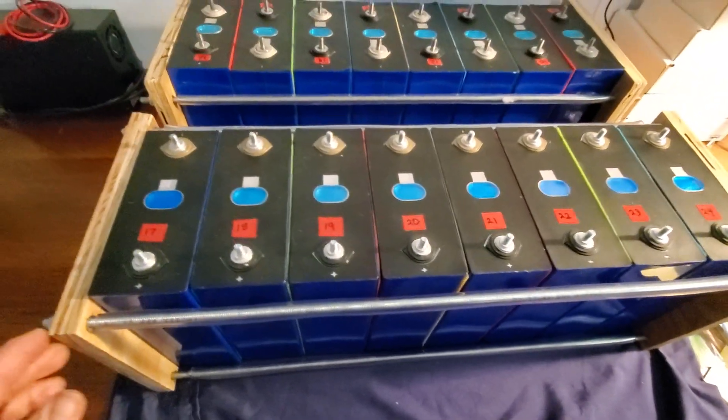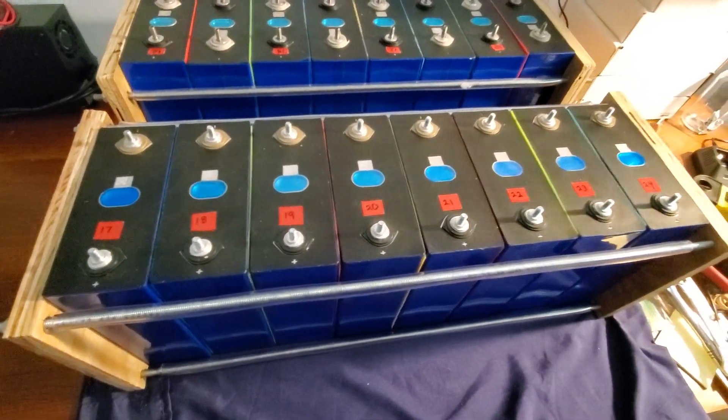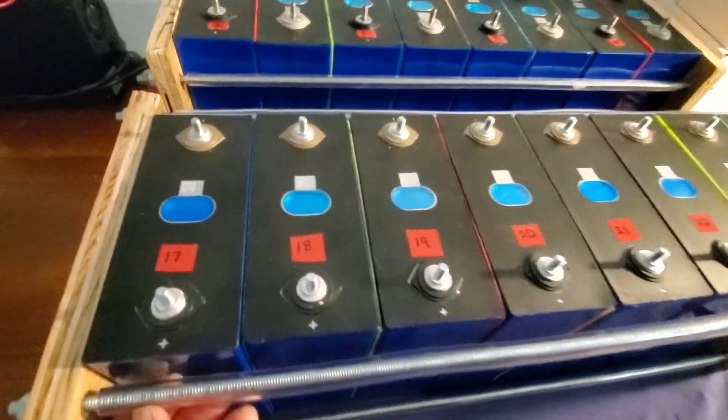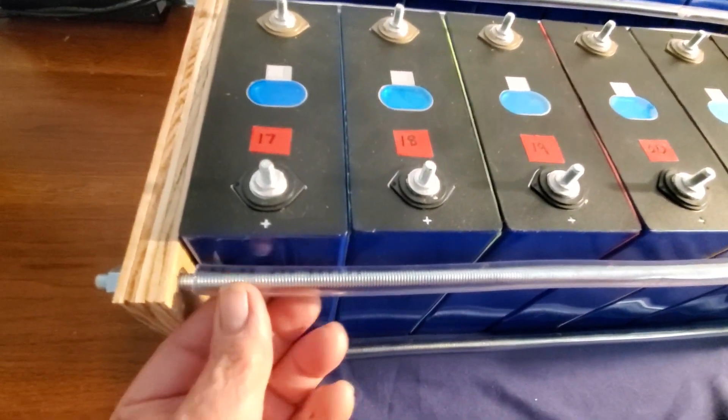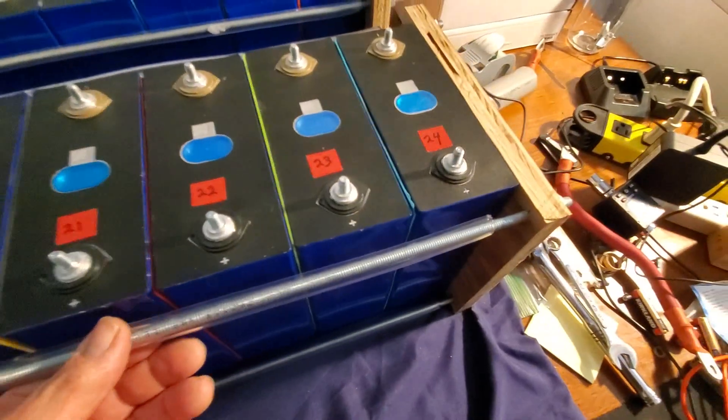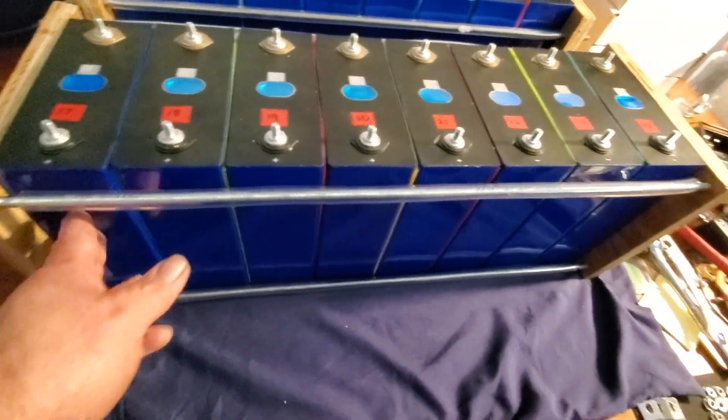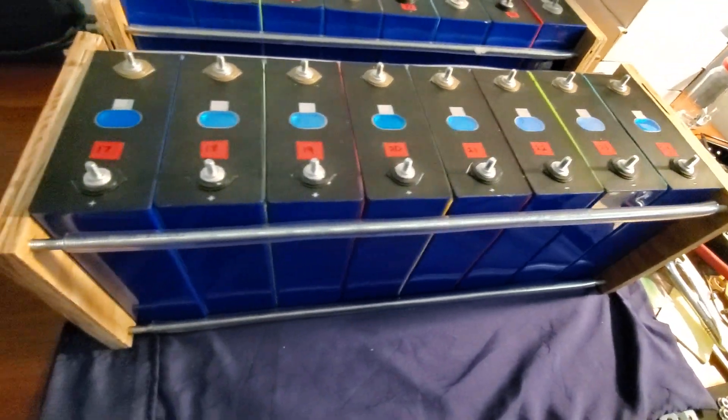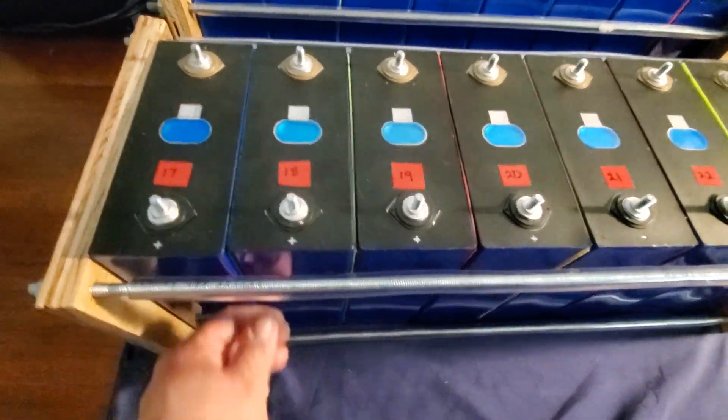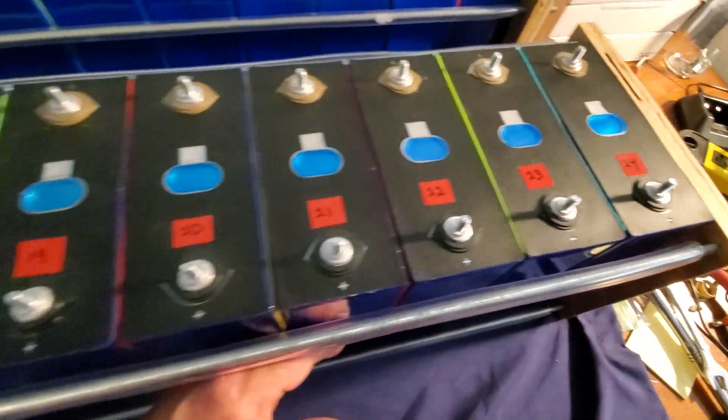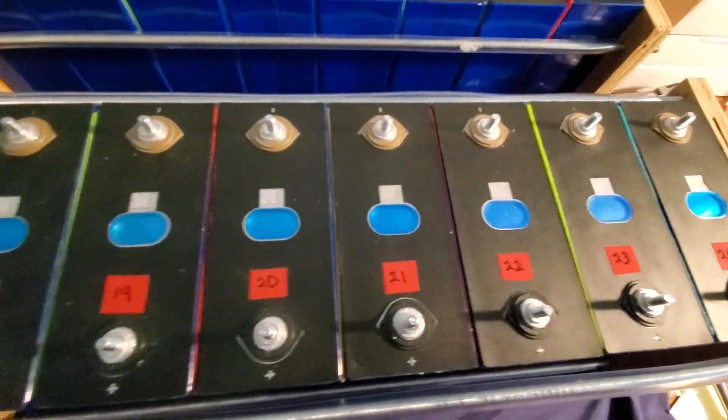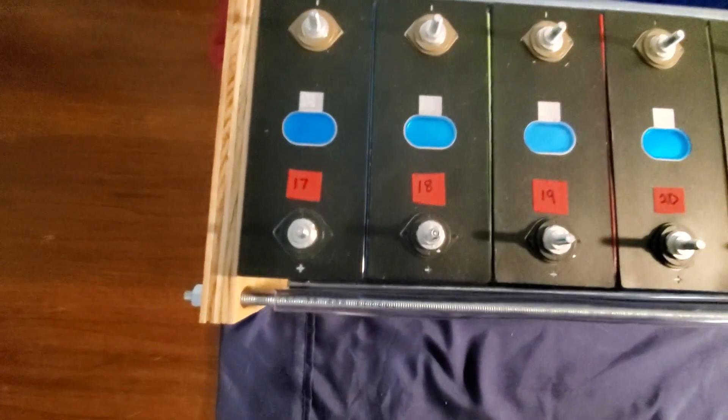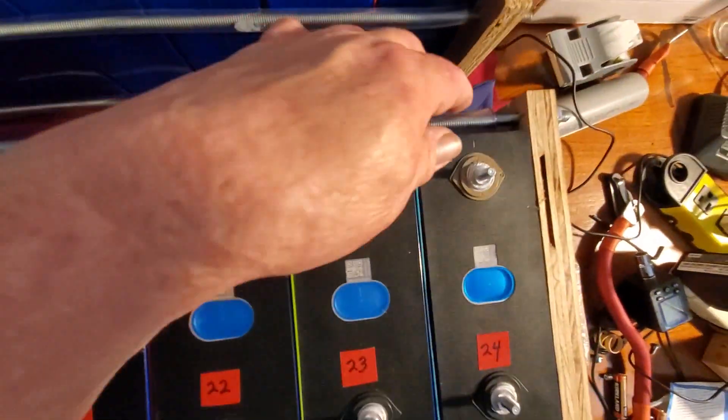You're not really wanting to overpress them, but you're wanting to make them tight. When I built these I went ahead and put plastic tubing on this steel rod just to keep it from connecting these batteries. You also got to make sure your inserts are not sticking out, and that all the batteries are nice and flush before you tighten it, with the same gap on all sides.